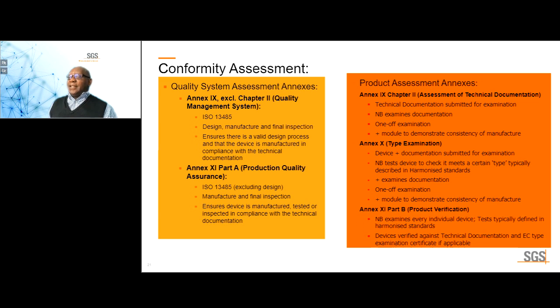Then Annex 11, Part B, production verification. This is where the notified body examines every individual device and would conduct tests typically defined in harmonized standards. Devices verified against the technical documentation and type examination certificate if applicable. In other words, you could combine Annex 9 and aspects of Annex 11 Part B.